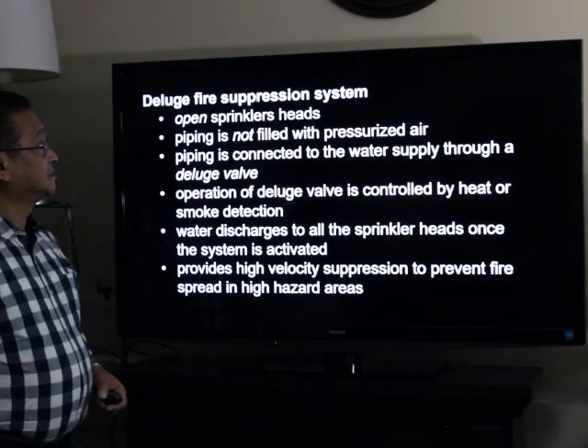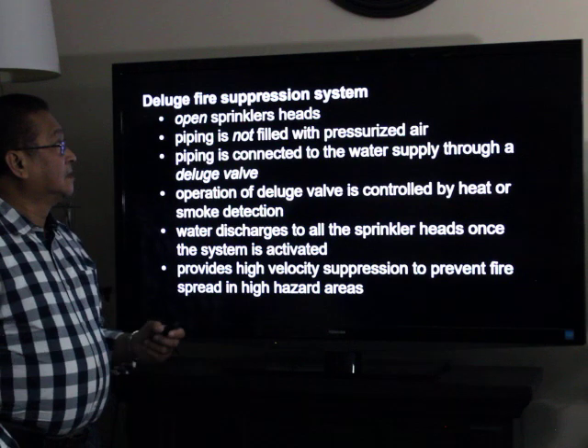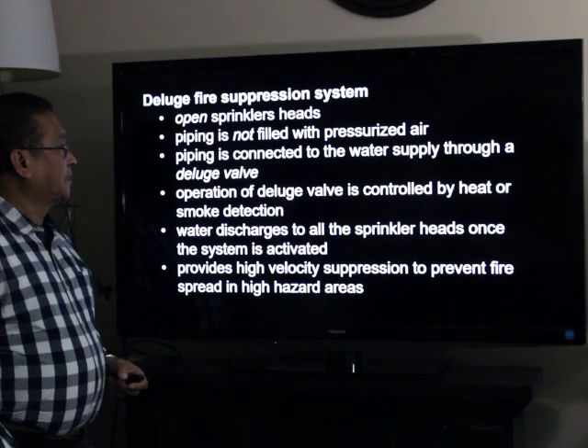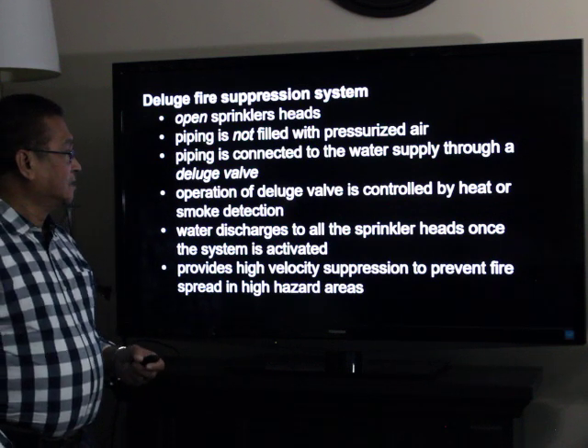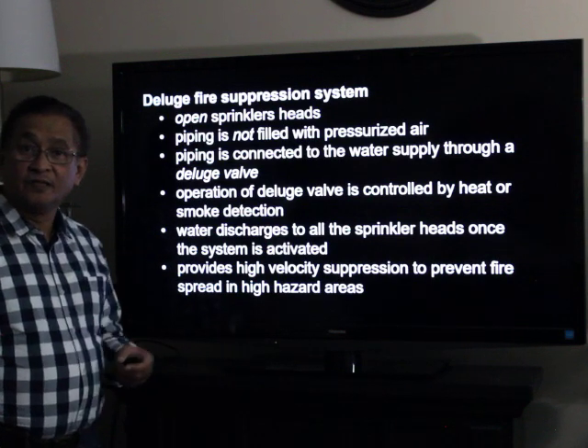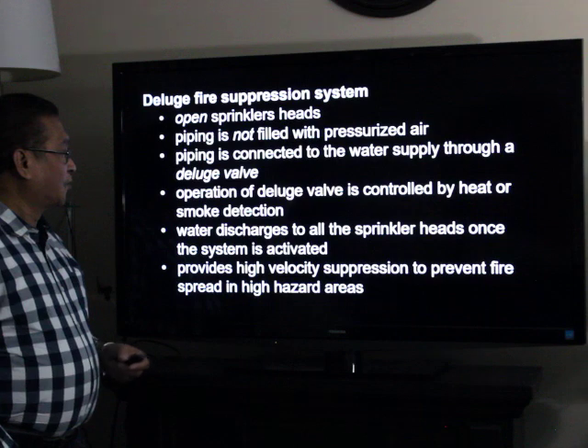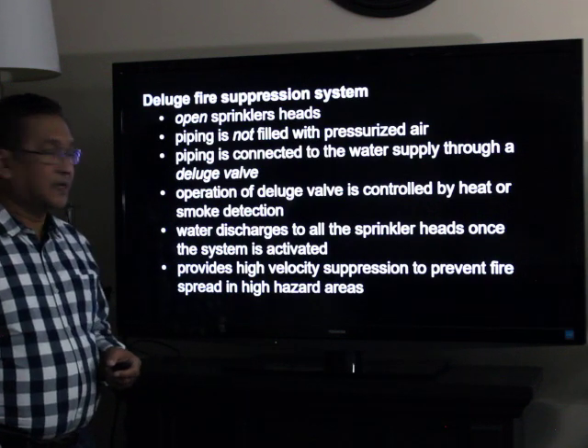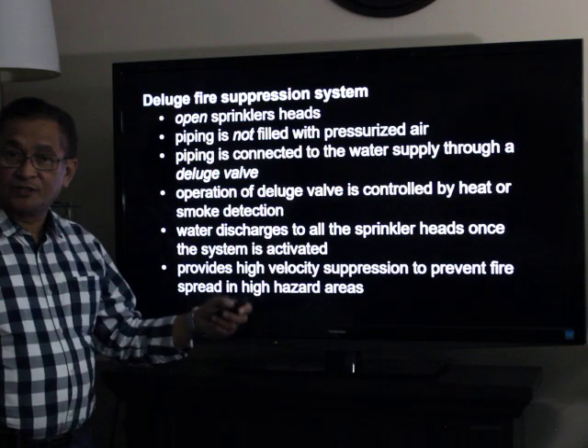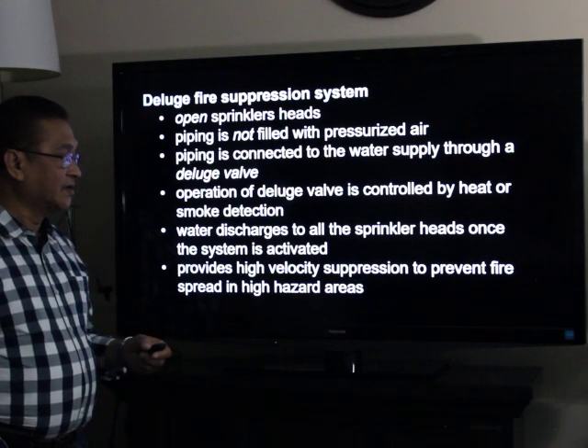The deluge fire suppression system is the only system having open sprinkler heads. The piping is not filled with pressurized air and is connected to the water supply through a deluge valve. The word 'deluge' comes from the meaning to inundate or to flood. Operation of the deluge valve is controlled by heat or smoke detection. Water discharges to all of the sprinkler heads once the system is activated, providing high-velocity suppression.